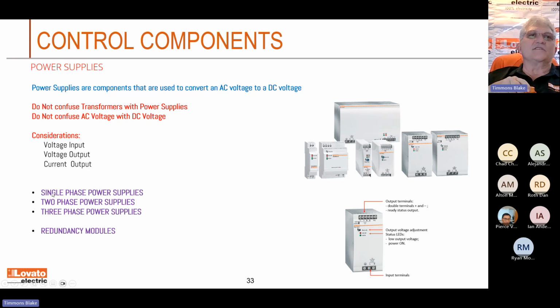But you can see that these come in single phase power supplies, two phase power supplies. They also come in three phase power supplies. So a lot of times on the single phase power supplies, you might build your control circuit with 110 volts and then decide you need 24 volts to run some DC stuff. Or you do a step down that way, or you can just go directly from a three phase right into 24 volts DC. Okay. And then we also mentioned the redundancy modules. So if I create a 24 volts DC and the only thing I got is a 20 amp power supply, but I really need 40 amps out there.